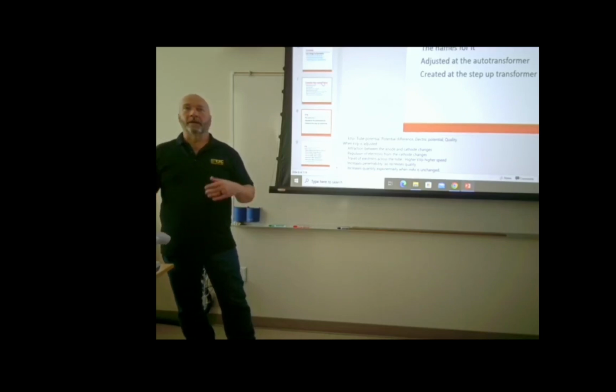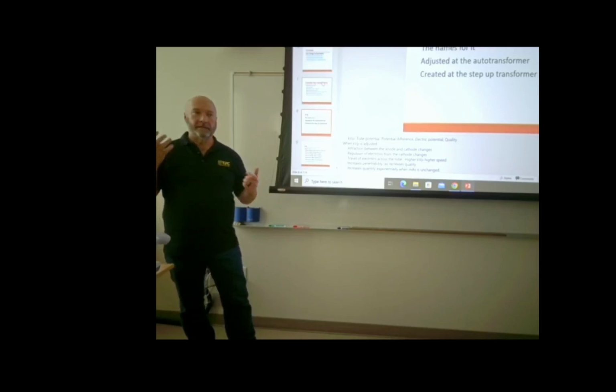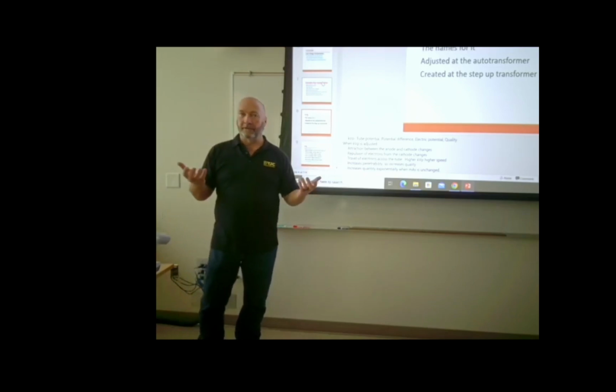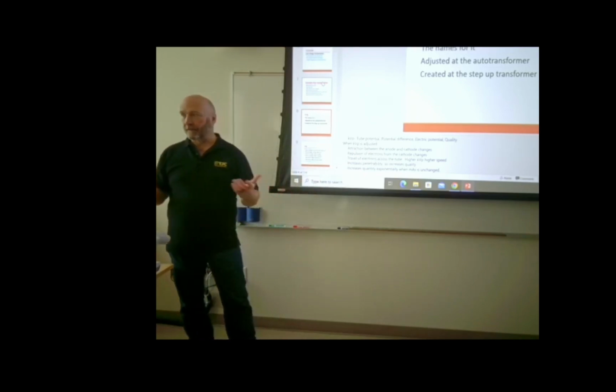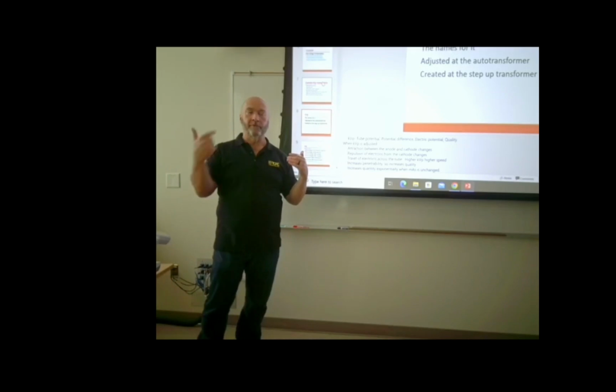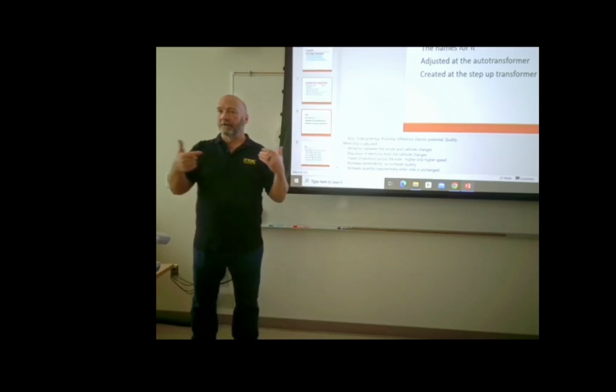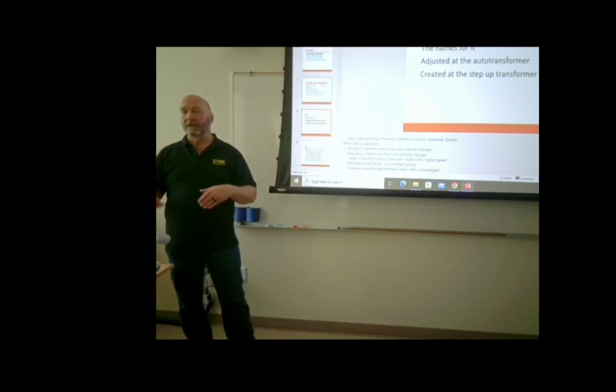So what kVp controls in the X-ray tube is that potential difference between the cathode end of the X-ray tube and the anode end of the X-ray tube. The difference between 50 kVp and 100 kVp is the difference in that charge. So the higher the kVp, the faster those electrons travel from cathode to anode, right? So the only thing that you're really changing inside the X-ray tube whenever you increase your kVp is the speed of those electrons as they travel across the tube.